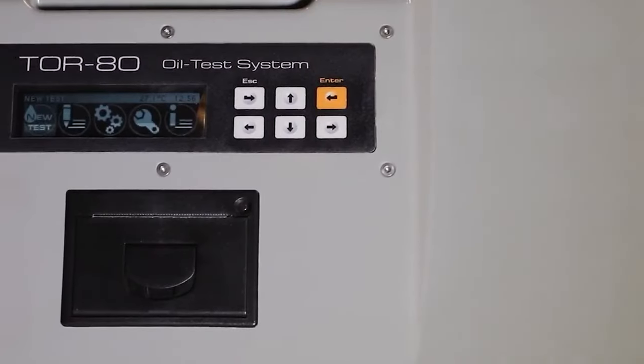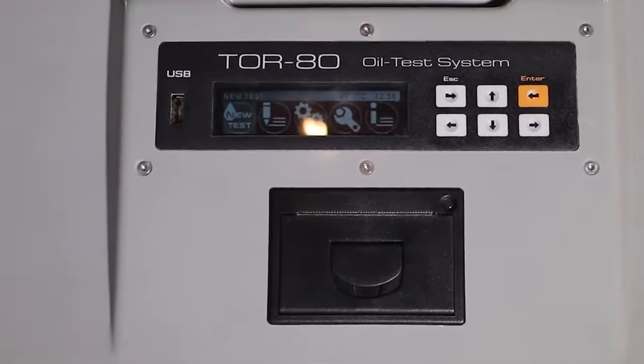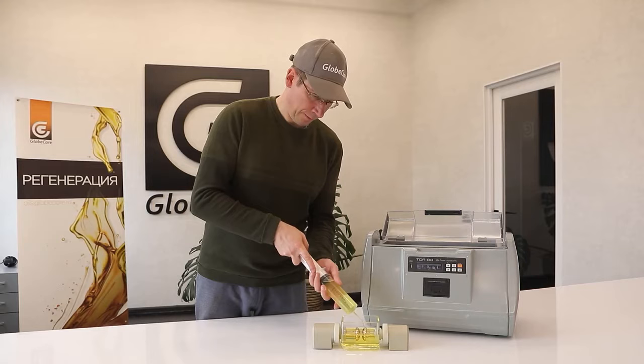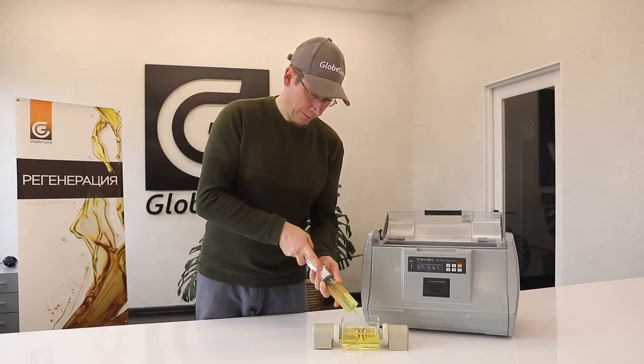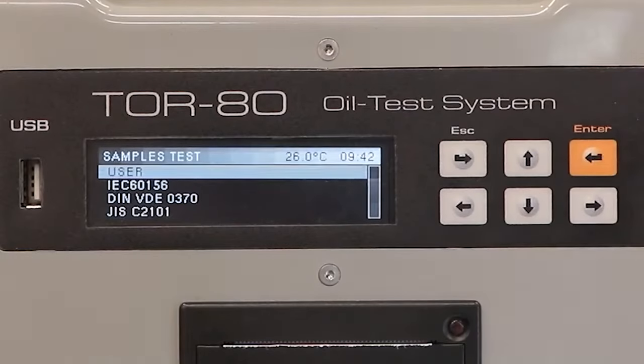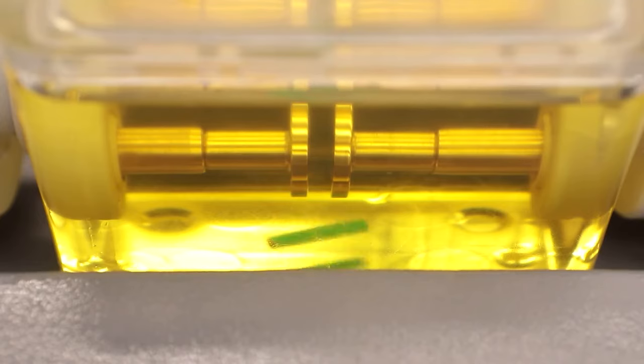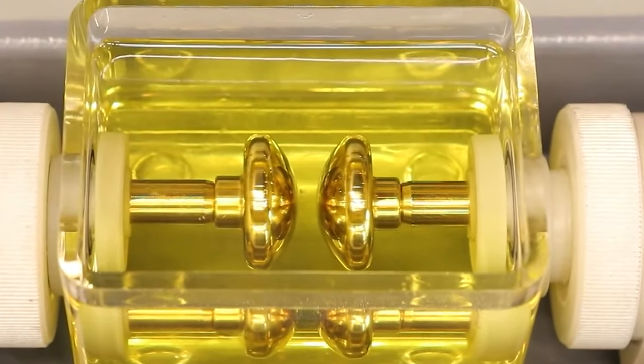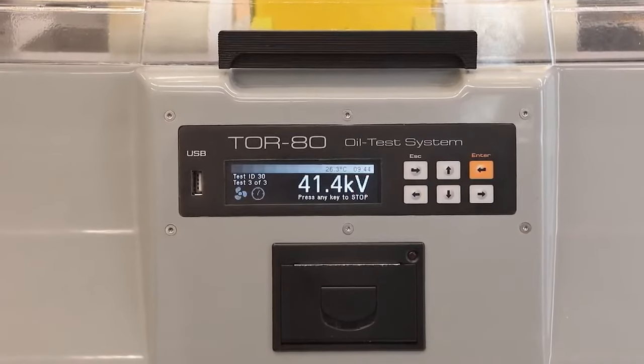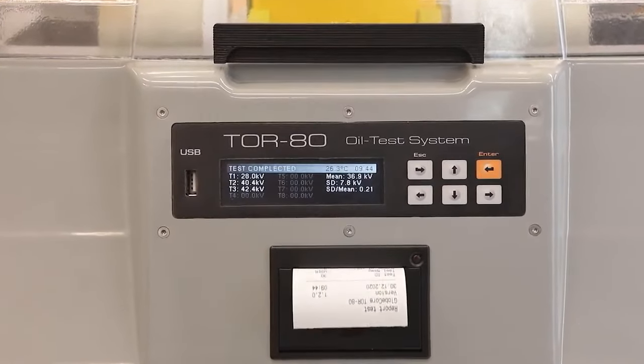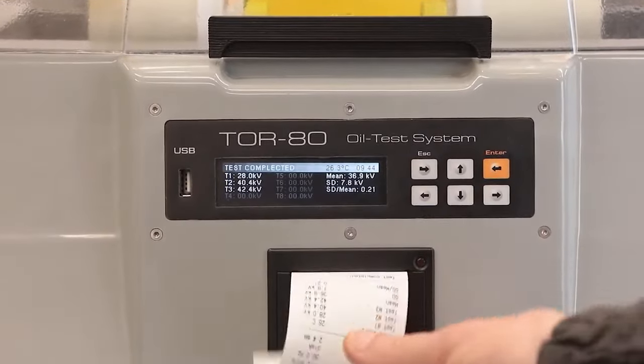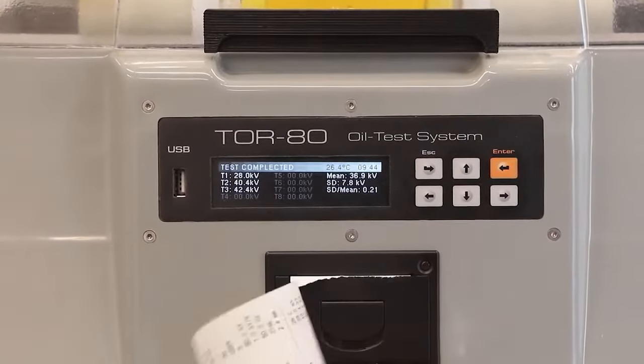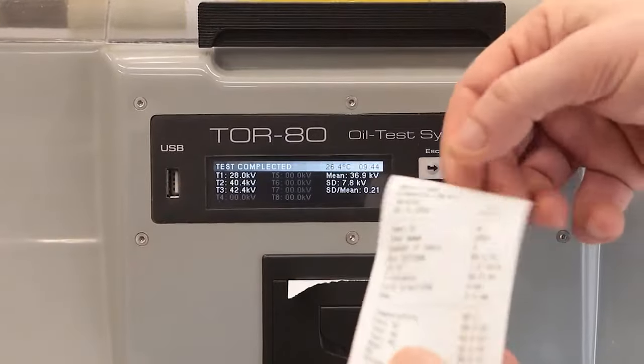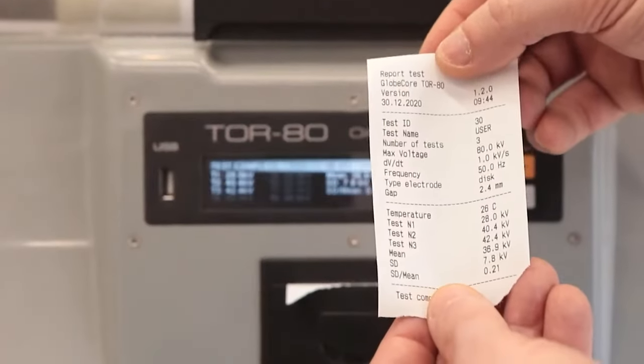The oil breakdown testing process is simple. The operator must connect the device to the mains, insert the measuring cell, fill it with oil, select the required standard, and start the process by pressing the corresponding button. The TOR-80 will do the rest by itself automatically, after which the first measurement of the breakdown voltage in kilovolts will appear on the display. The entire process takes only 5 minutes. The breakdown voltage measurement error does not exceed 1%. This precision is achieved through technologies developed by GlobeCore and new industry standards.